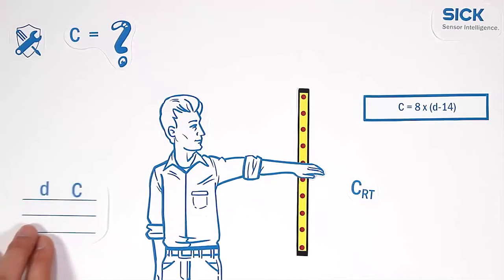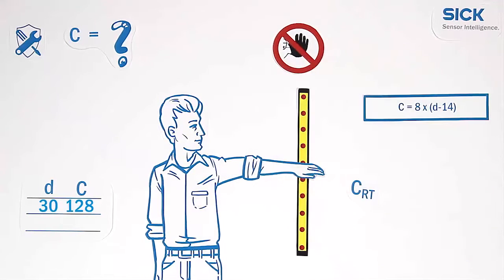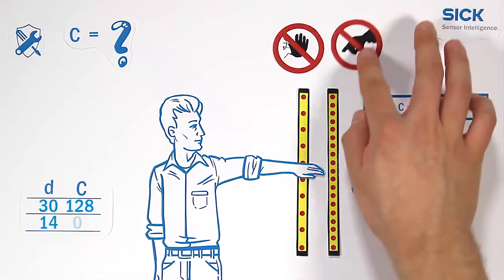In the case of a 30 mm resolution, we receive a value c of 128 mm ensuring hand detection. With the finger protection resolution of 14 mm, c becomes zero.